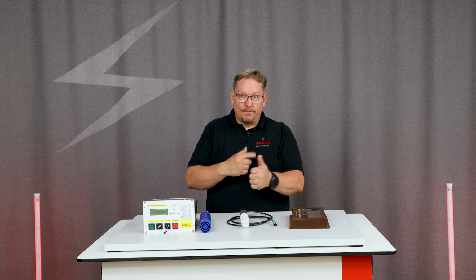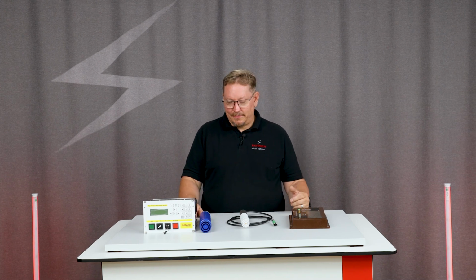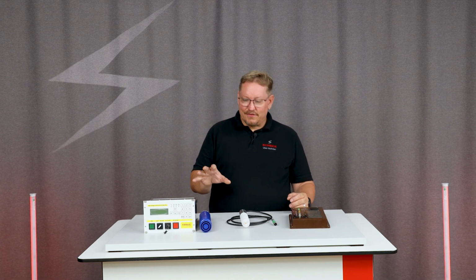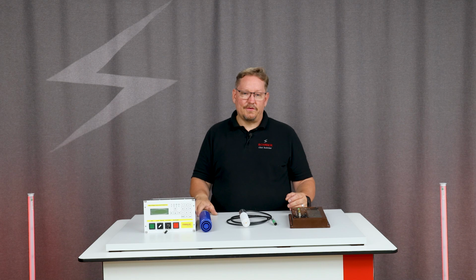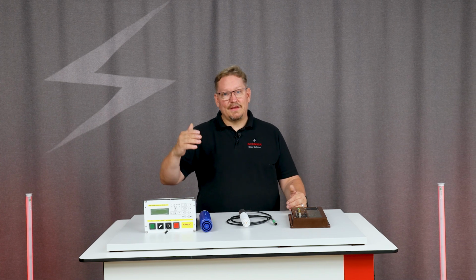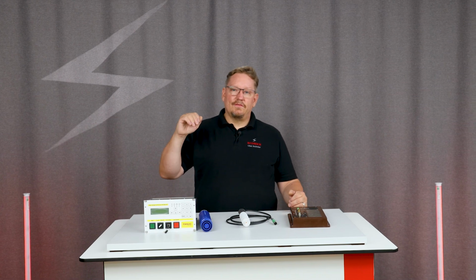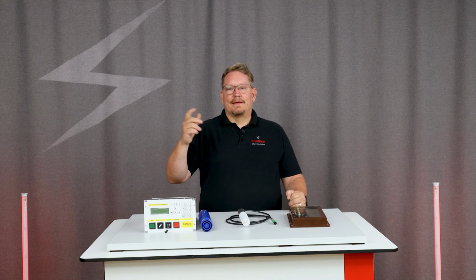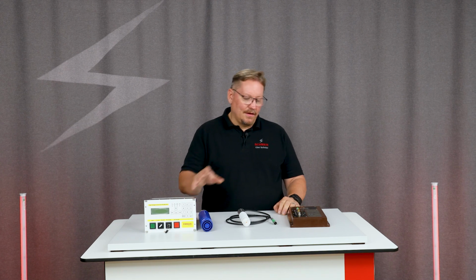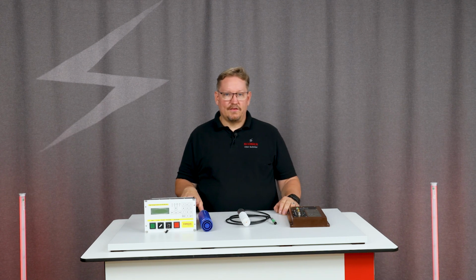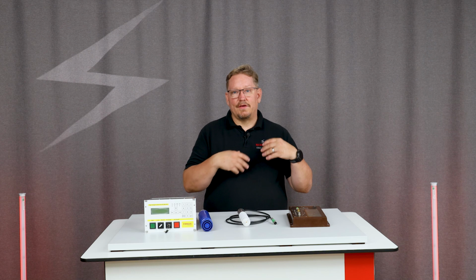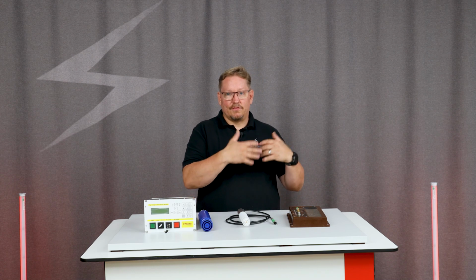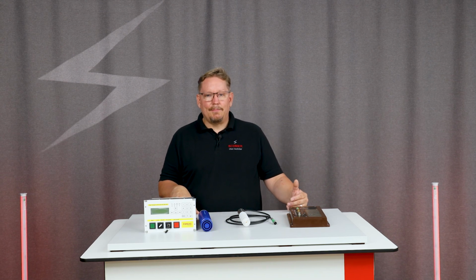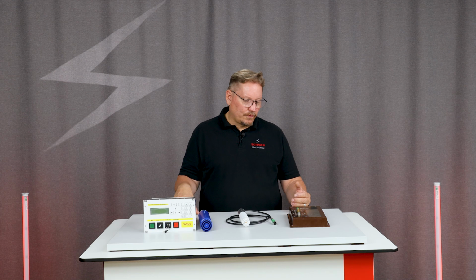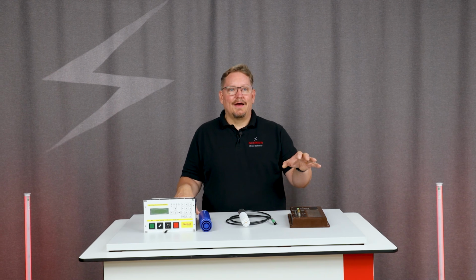And then I have to take all protective measures. This means that the last advantage I might have with such a system is that the discharge time is somewhat shorter. This means that if I switch off the high voltage, I can discharge a little faster, which we partially compensate for here through the redundant measurement. We have two discharge resistors, so the measuring resistors are also discharge resistors, and therefore also discharge faster.